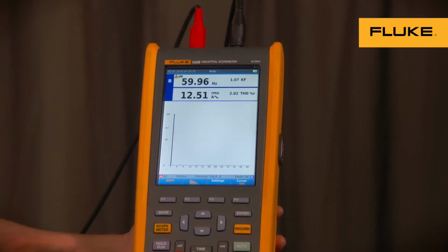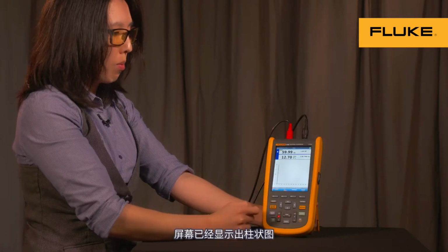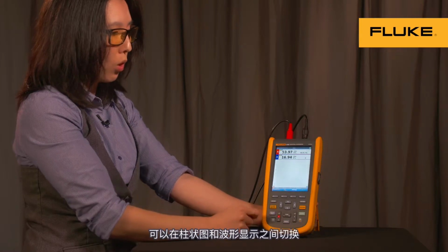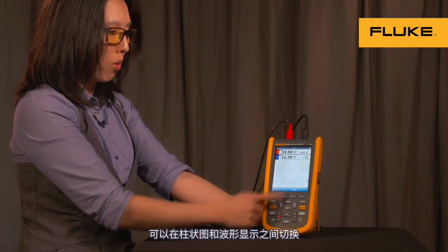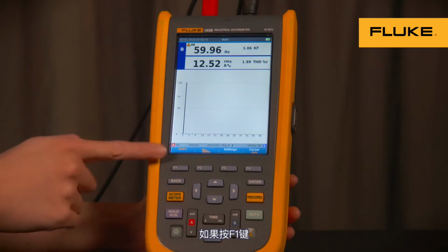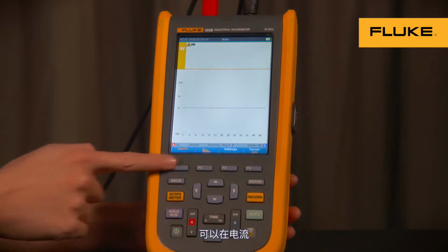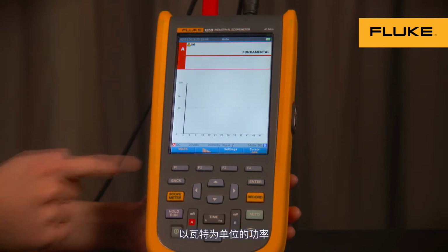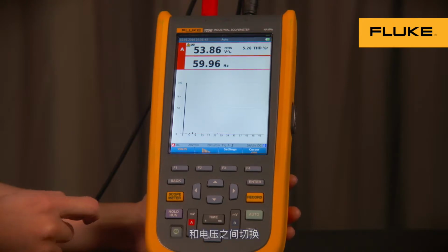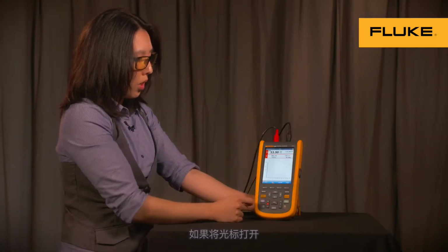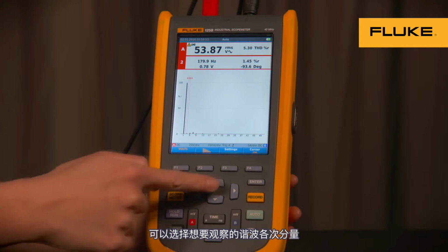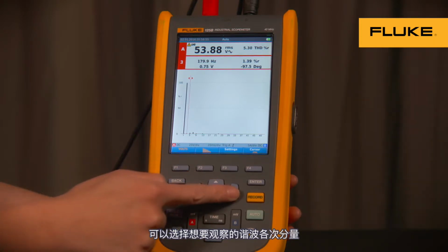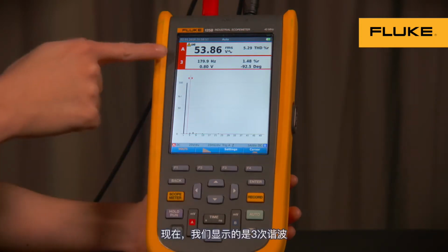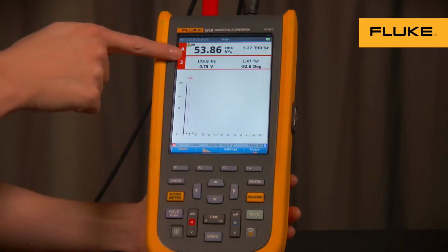Press enter. You'll see here that you have your histogram display. If you use F2, you can toggle between histogram and waveforms. If you press F1, you can toggle between current, power, which is displayed in watts, and voltage. If you turn the cursor on, you can now select which power harmonic you want to look at. So right now we're currently on the 3rd harmonic.